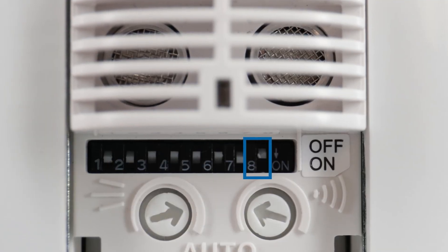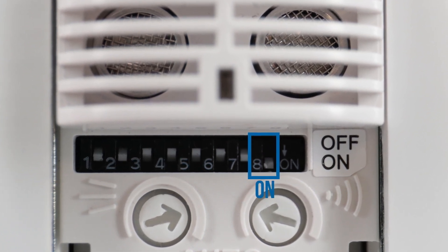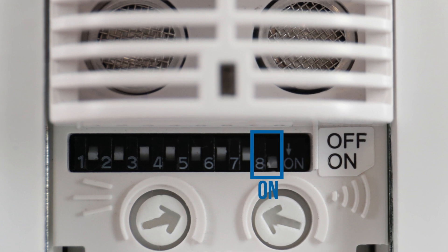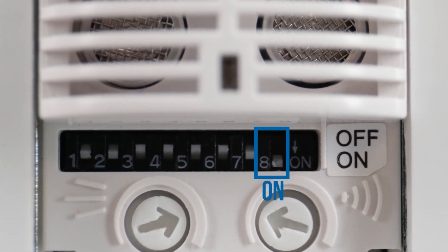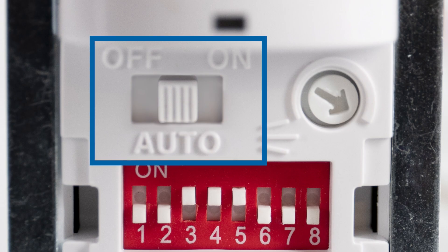DIP switch number 8 enables ultrasonic technology in the dual-tech sensor. With PIR sensors, DIP switch number 8 has no effect. The mode selection switch takes you into programming mode and also allows manual lighting control. In the on position, the lights are always on. In the auto position, the lights defer to the sensor settings. And in the off position, the lights are always off.